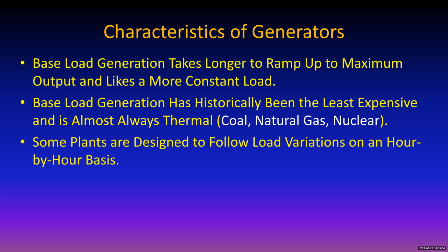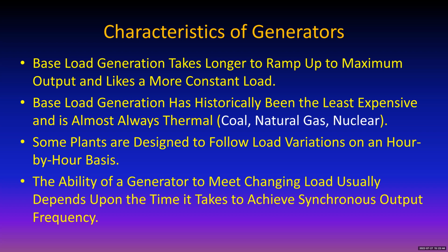Here's a partial answer to the question. Some plants are designed to be able to follow the load variations on an hour-to-hour basis. Other plants are designed differently, and whether the generator can meet the changing load usually depends on the time it takes to achieve synchronous output frequency - in other words, get up to speed. So that's why utilities are required to have some generators already running at full speed so they can synchronize with the grid faster. That's where we get the concept of spinning reserve versus non-spinning - in other words, they simply shut the thing down during those nice balmy spring and fall days where your peak load goes down a little bit. In fact, maybe even shut some down and do a little maintenance work.